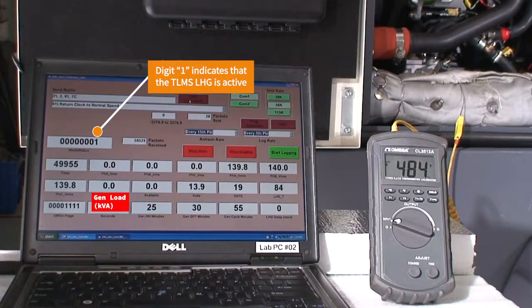In a few moments we will apply 10 kilowatts of electrical load using the load bank. The load will be displayed on the screen where it says Gen Load in kVA. Instantaneously when the load bank is turned on, the LHG will automatically disconnect. The LHG control system has current measurement transformers which are calculating the electrical load on the generator, causing the LHG to respond accordingly whenever there is electrical load applied.